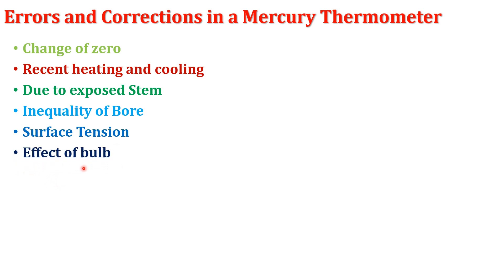The next error is the effect of the bulb. The bulb is a glass material and a bad conductor of heat, so it has an insulating effect. Due to this, mercury inside the bulb may not attain the temperature of the bath. To correct this error, the bulb should be thin-walled and the thermometer should be kept in the bath for a long time before measuring temperature to obtain an accurate reading.